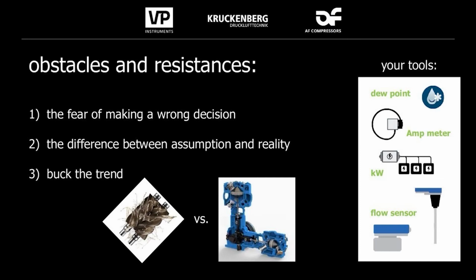obstacles and resistance you will face. Of course, the fear of making a wrong decision is imminent in a consultation process. It's always quite easy to swim downstream, but bucking the trend is important. And your tools are dew point measurements, amp meters, kilowatt measurements, and I really suggest not just using amp meters. They are good for the beginning, but later on going for the complete kilowatt measurement is important. Different kinds of flow sensors show the client what the real figures are, the difference between assumption and reality. And then you can even suggest completely new technologies or solutions for the client.